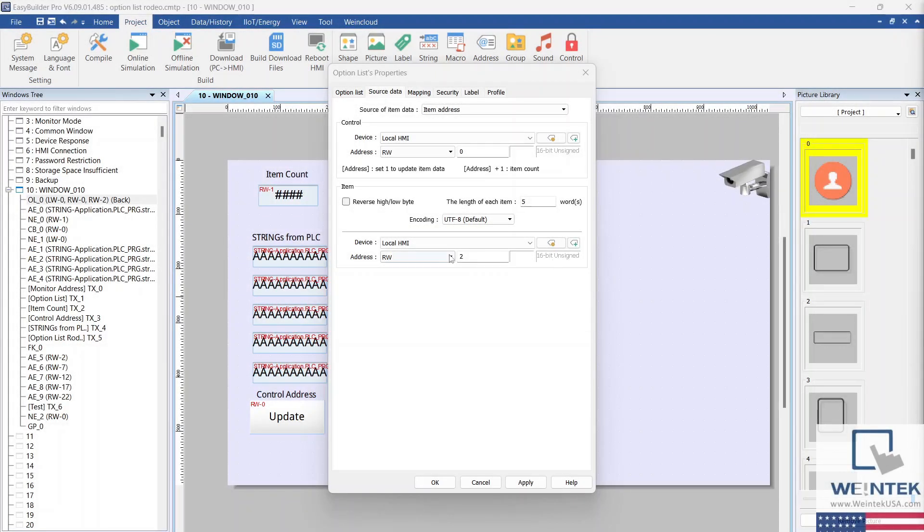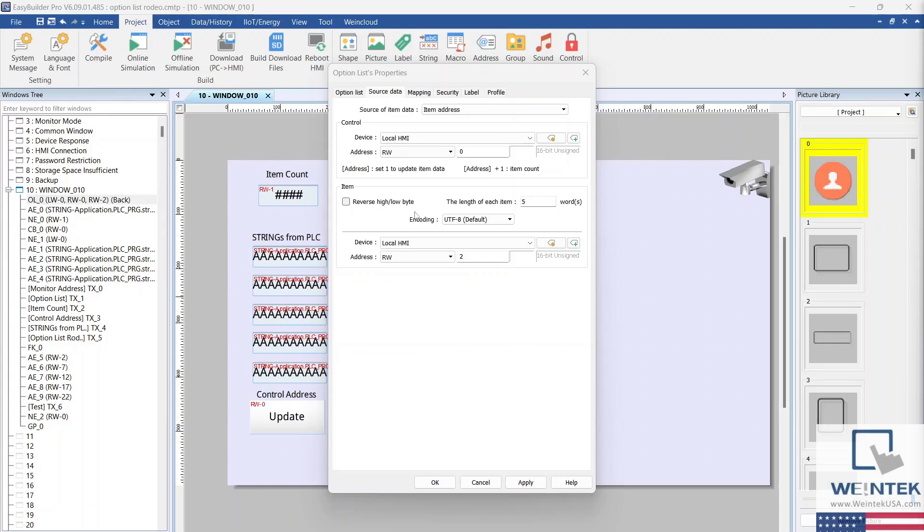Within the Items section is where we configure the addresses of the items within the list. The length of each item determines both the word count of the item and the address of the next item in the list. For example, the first item in the option list will have the address of RW-2. Because the length of each item is 5, the next item in the option list will have an address of RW-7. The next item will have an address of RW-12, followed by RW-17 and RW-22.